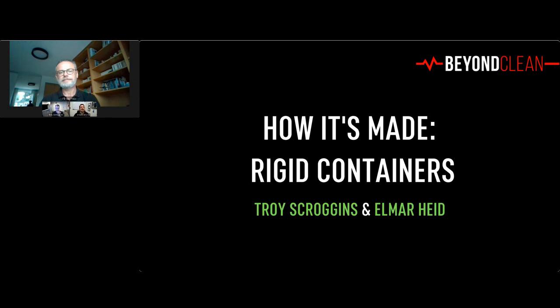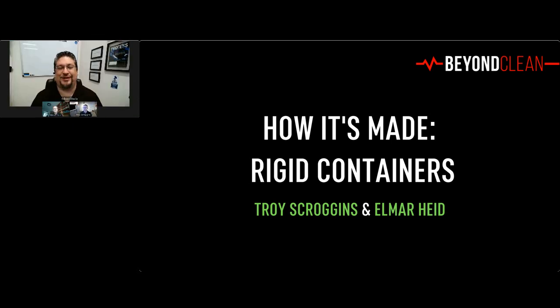Okay. And again, I think it has to do with the pre-vacuum. We're so used to things coming down through the container that when they see a solid bottom, they think, well, that can't possibly be pulling the steam out of that set. But it's not pulling it in a unidirectional downward way, right? It's able to escape the air anyway. So yes, it is an urban legend that you cannot stack those solid bottom trays.